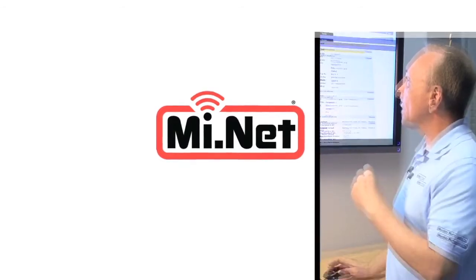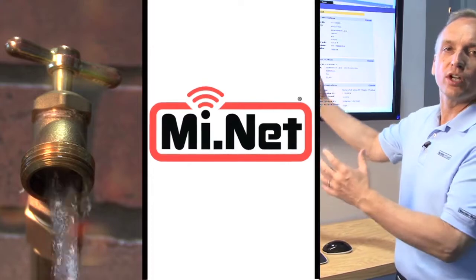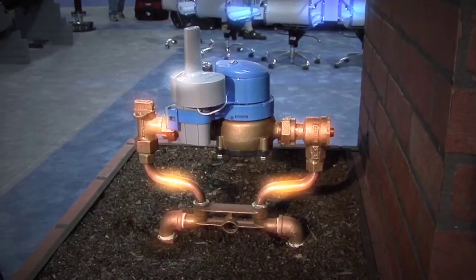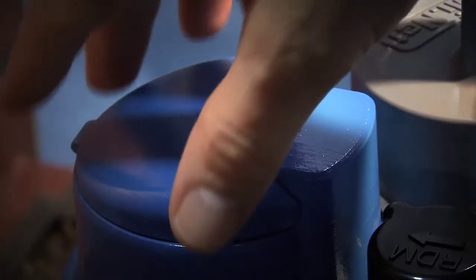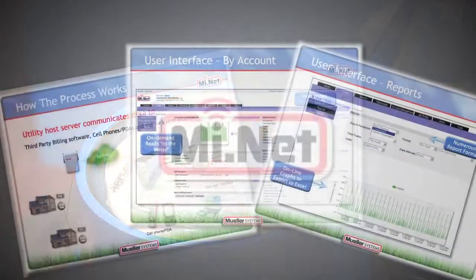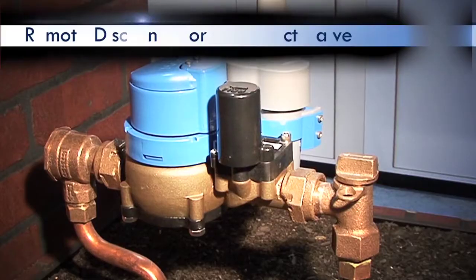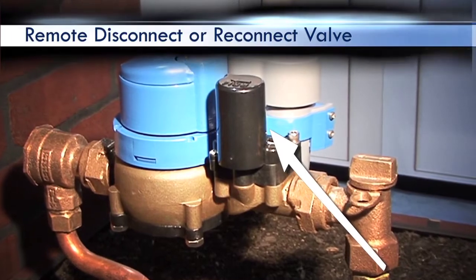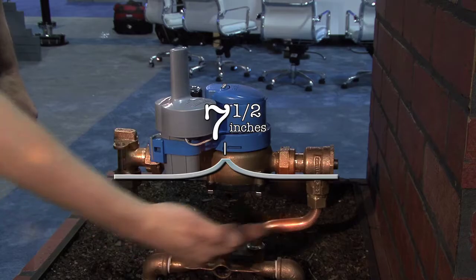This new product allows utilities to manage their water from their desktop. What we're going to show you is a water meter — a nutating disk water meter with an absolute encoder register, a two-way fixed network (our Mi.Net system), and a new component: the remote disconnect or reconnect valve. All in a 7.5 inch laying length, with no re-plumbing or re-piping of your systems. Simply remove the existing meter and put the new meter back in, all in that 7.5 inch laying length.